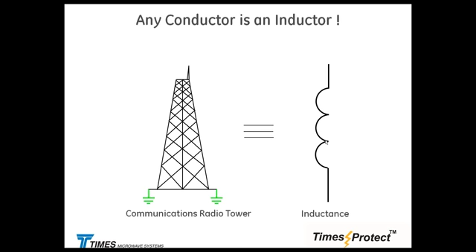Remember the rate of rise time of that current, the di/dt. If you want to figure out what inductive voltage drop we are going to experience, you simply take the inductance of the tower or the cable and factor that into the rate of rise time and the peak value of that current to figure out the total amount of inductive voltage drop across it. So basically every conductor in the air will become an inductor, especially with a di/dt.